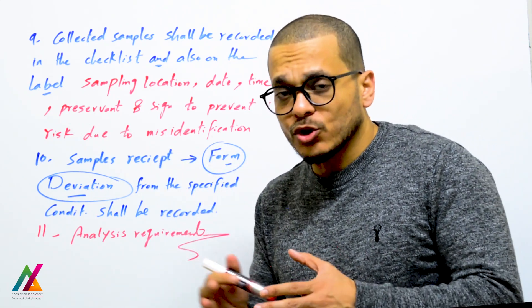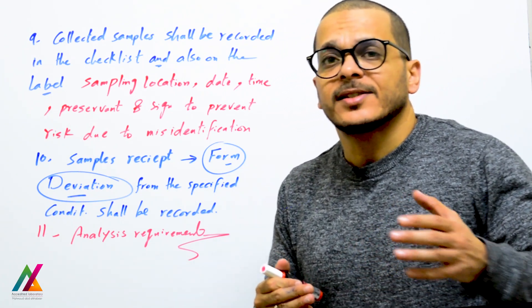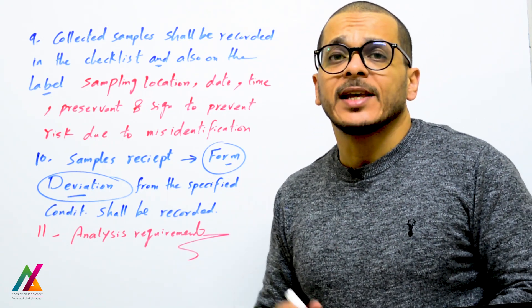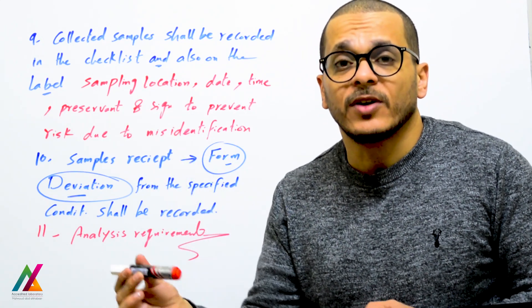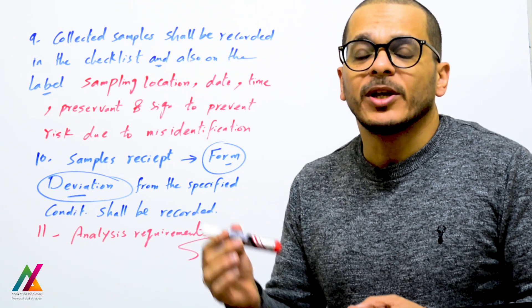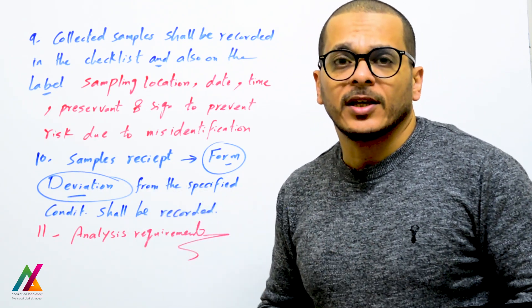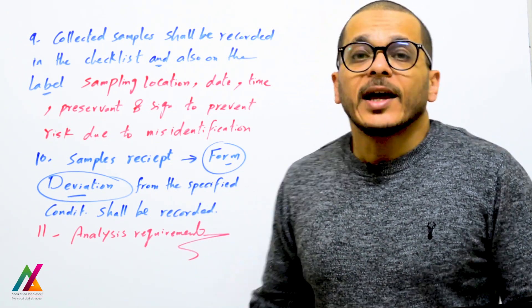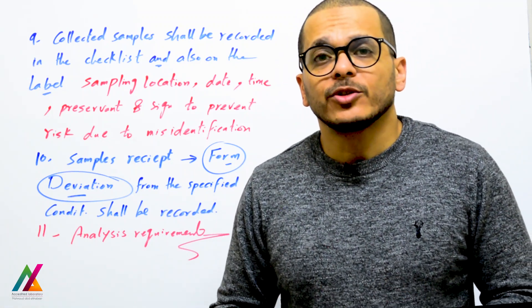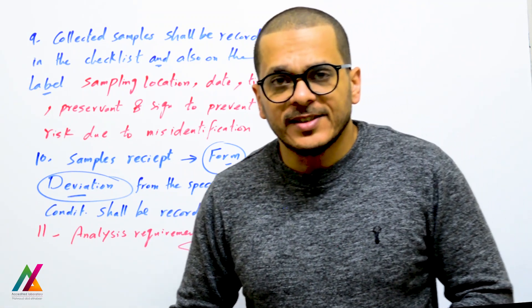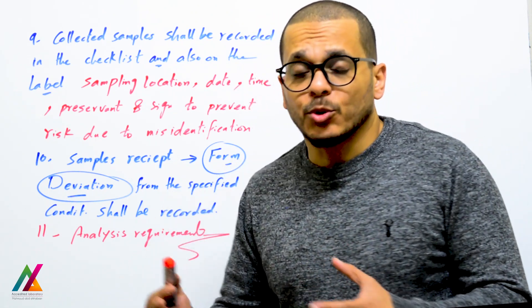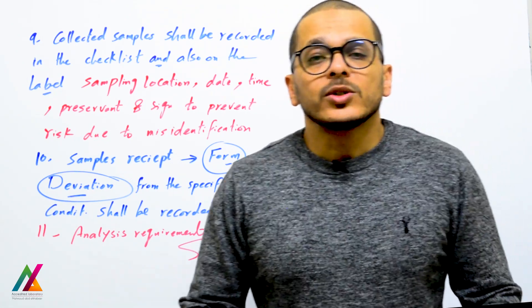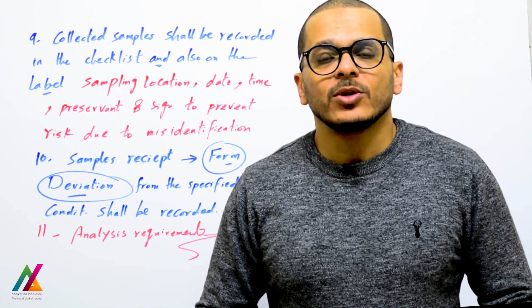For other analytes, analysis can take six hours, one day, or more — in that case, samples can be preserved in the freezer or fridge at the specified temperature. These freezers shall also be equipped with a data logger at the required temperature setting, and temperature shall be recorded daily in a specific form. This covers the procedure required for handling, transportation, and storage of test items, which you can adapt according to your lab's requirements.